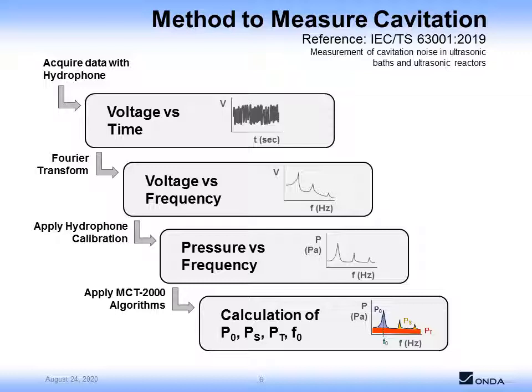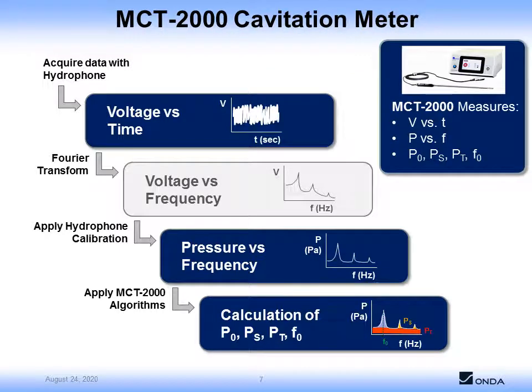Now you have SI units on both x and y-axis. And the pressure spectrum can be analyzed to quantify the pressure from the stable cavitation, transient cavitation, and the direct field. The instrument used in this study is called the MCT2000, which follows this method and saves the following layers of data: namely, the voltage waveform, the pressure spectrum, and the calculated parameters.